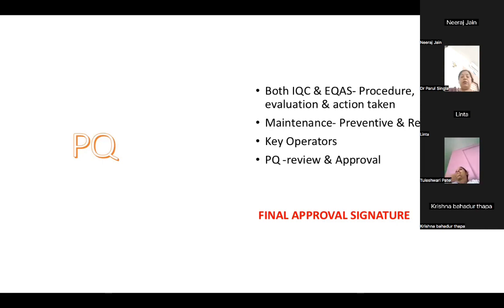You can mention that we will be doing the same protocol, or you can mention your own protocol, like we will be doing accuracy and reference interval verification, and how many samples you will be doing. If it is a high volume test, more tests can be done. But if it is a low volume test and you are receiving very few samples, you can define your protocol, how much you will be doing. This is the lab's prerogative. If you already have one instrument of the same make and you are taking a second equipment, you can also say that we will be doing only the inter-instrument correlation. It's up to the lab to define the protocol of performance qualification.